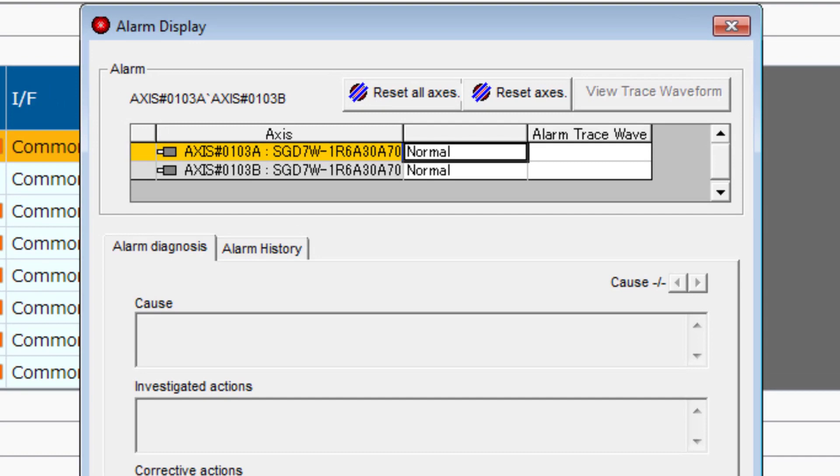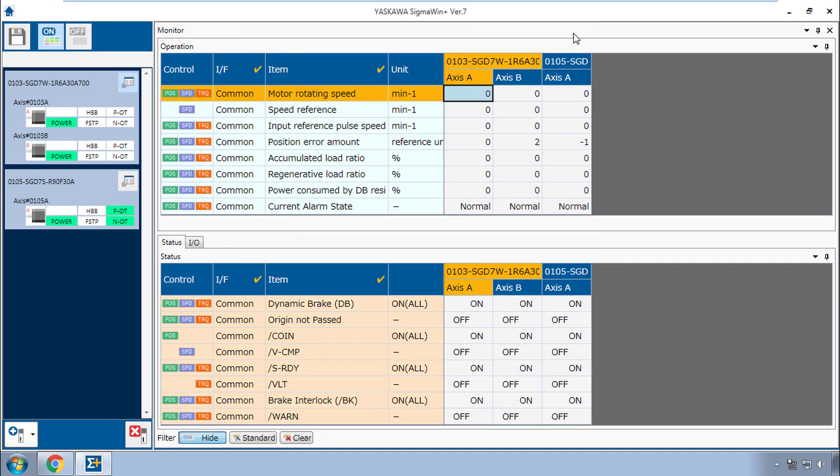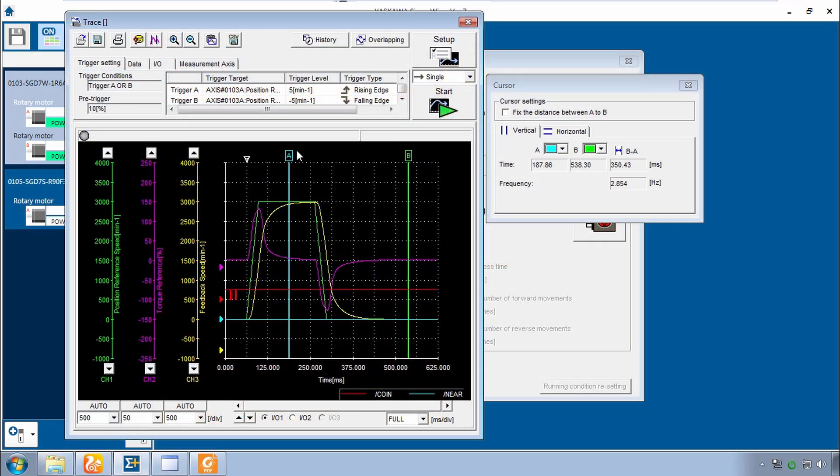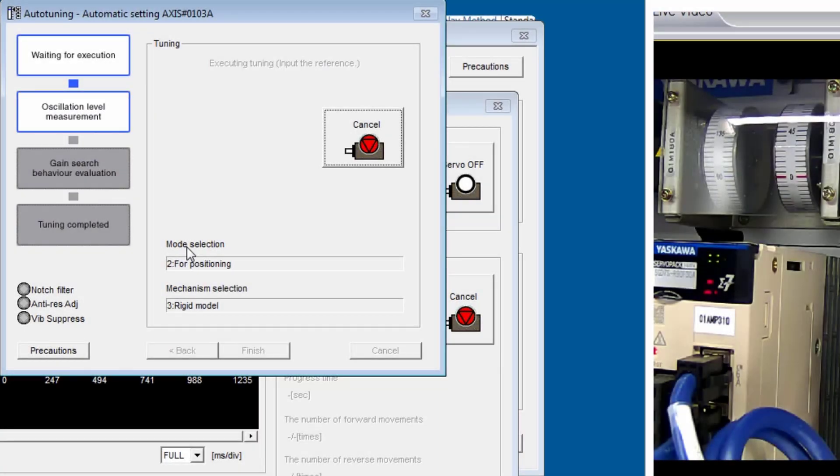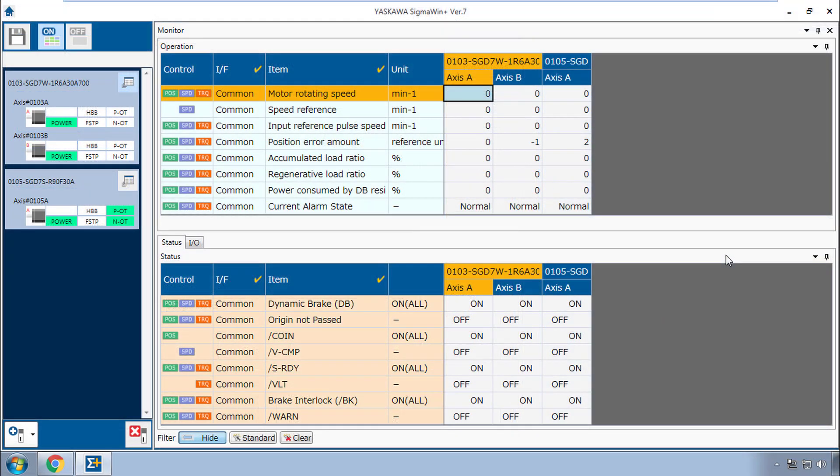Now I can take advantage of the alarm diagnosis, alarm history, alarm trace. The feedback monitors for all the axes can be seen at once. I can capture high resolution motor response traces for analysis and run through autotuning to maximize performance. These are just a few of the advanced servo diagnostic and adjustment tools available in Sigma Win Plus.